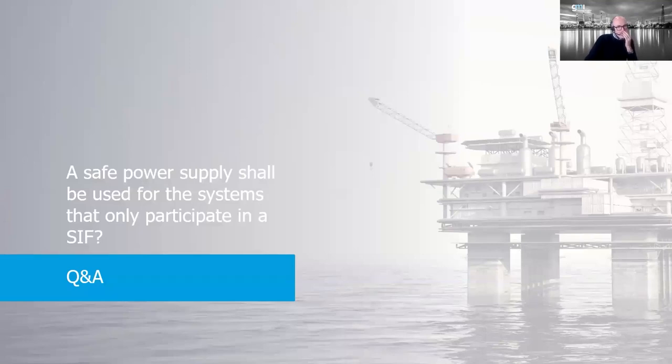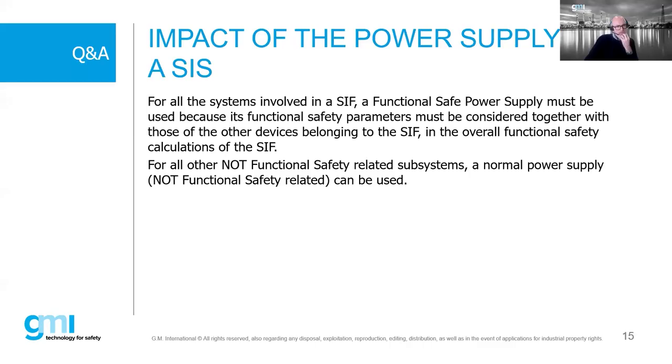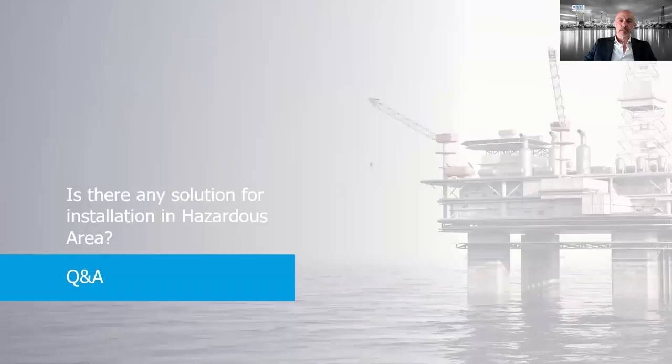A question: should a safe power supply be used only for the system that participates in the SIF? For the safety function, a safety power supply must be used - this is clear from IEC 61508. For other operations not related to functional safety but sharing the loop, a standard power supply can be used instead - it is not required, but of course it is suggested.